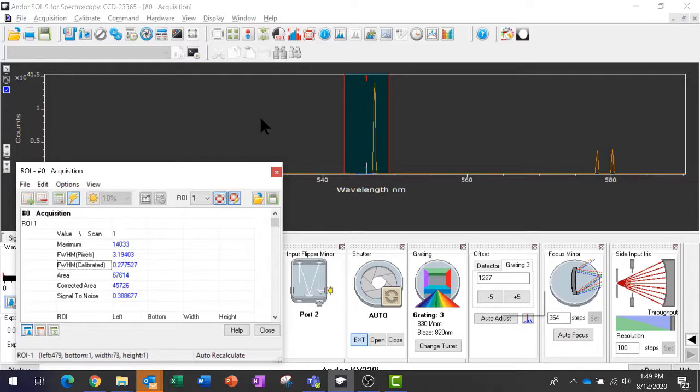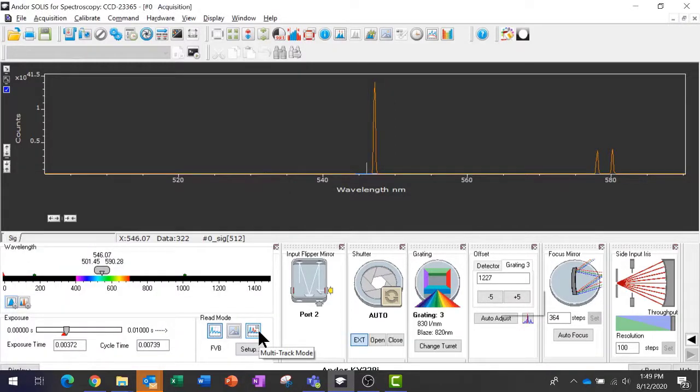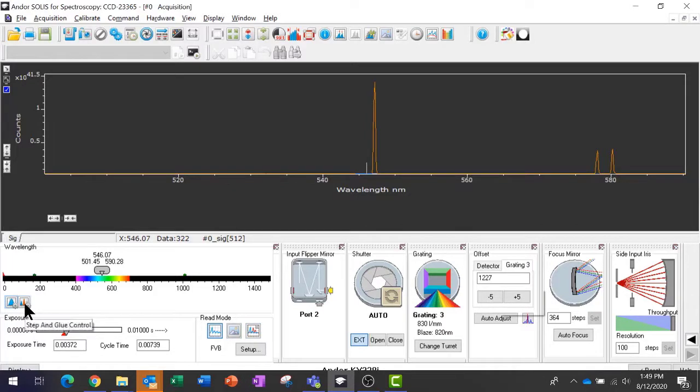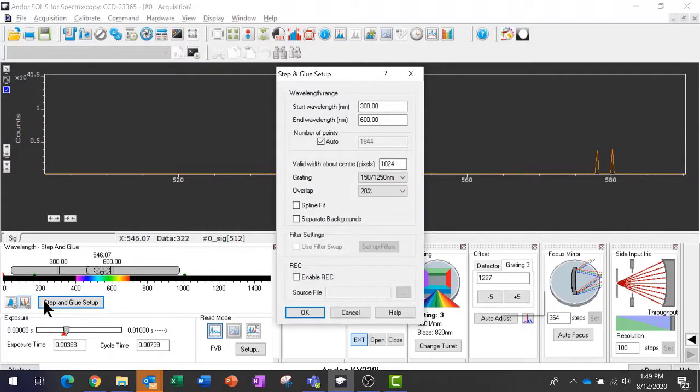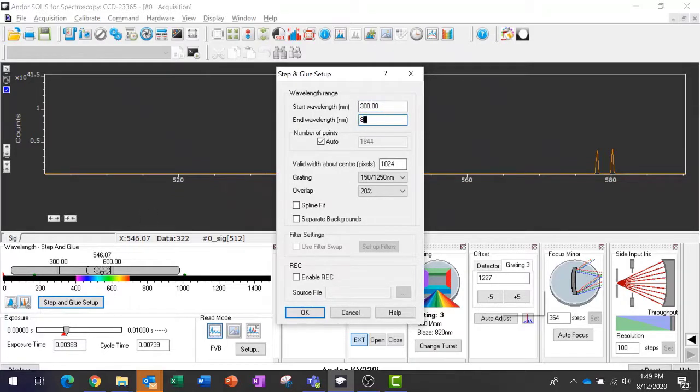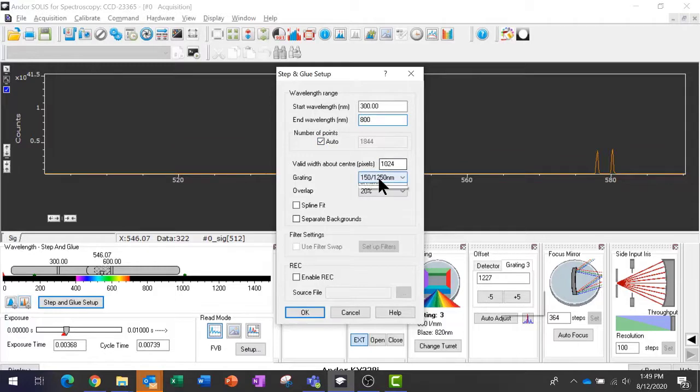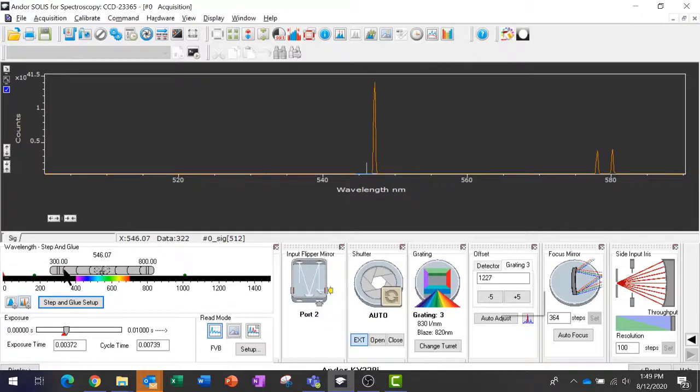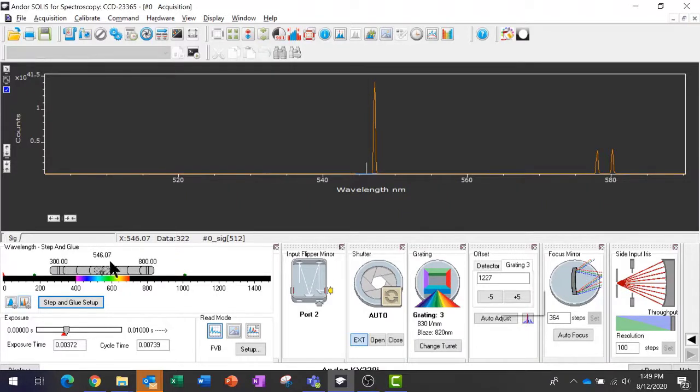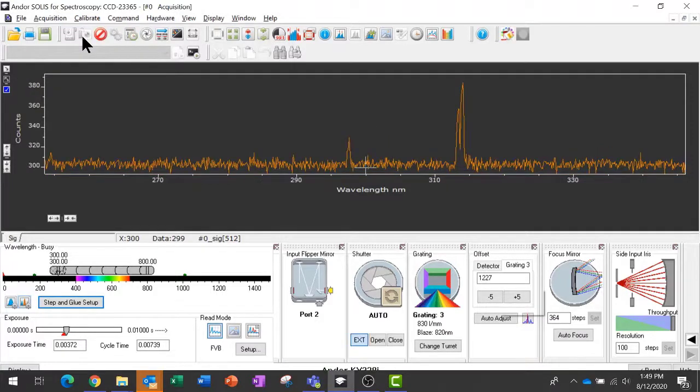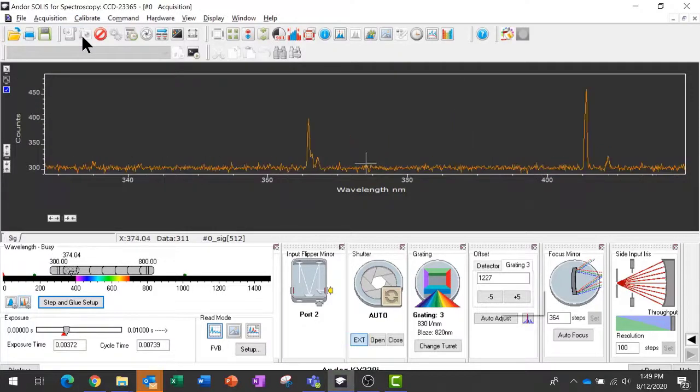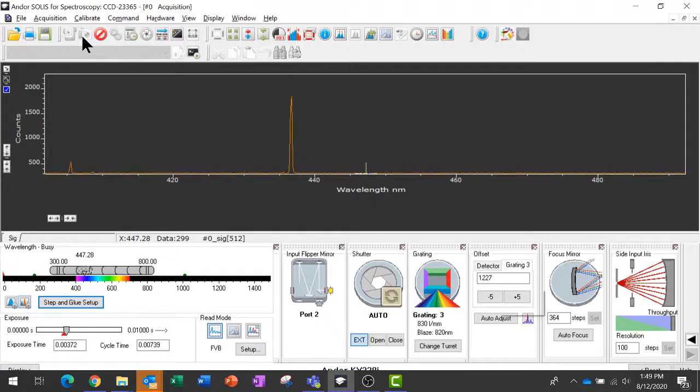So if I create an ROI, I see that my full width half max is now down to less than a third of a nanometer, about 0.28 nanometers. So what if I wanted to do a very high bandwidth measurement, that is to say, cover a large spectral width with very high resolution? Well, this is one option. I'm going to do a step and glue measurement. So to set that up, I'm going to go to the step and glue view here. And open the step and glue dialog. I'll give a start and an end wavelength. Perhaps I'll go a little further into the near IR. And the rest of it I'll leave at the default settings, other than the grating, which I want to specify my high resolution grating. Now you can see my range has been broken up into individual measurements that have the bandwidth of a single measurement using the higher res grating.